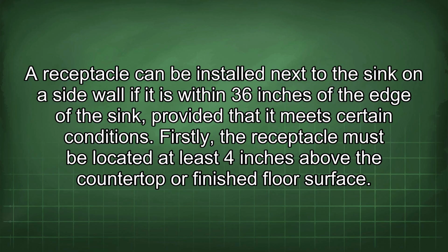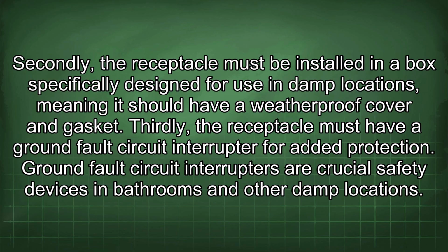A receptacle can be installed next to the sink on a sidewall if it is within 36 inches of the edge of the sink, provided that it meets certain conditions. Firstly, the receptacle must be located at least 4 inches above the countertop or finished floor surface. Secondly, the receptacle must be installed in a box specifically designed for use in damp locations, meaning it should have a weatherproof cover and gasket. Thirdly, the receptacle must have a ground fault circuit interrupter for added protection.